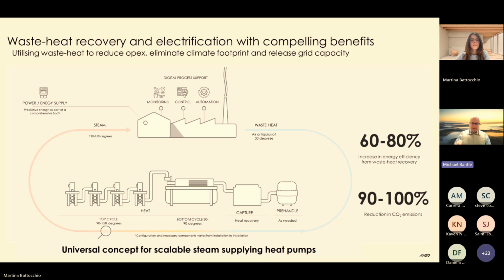Yeah. If we make this loop around the factory, we see that the waste heat energy is normally below 50 degrees, so we need to start our heat pumps at this kind of temperature, while the current boiler systems normally require up to 180 degrees or 10 bars of steam. So what we cannot do is supply 10 bar steam directly, just because of the high temperature lift.